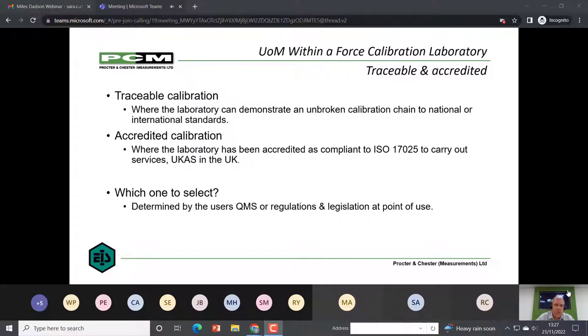And once you've decided, do you want a traceable or an accredited? And to be fair, most accredited calibration labs will offer traceable as well, and most likely be on the same equipment. Which one do you select? It is entirely down to either the quality management system of the company carrying out the use of the calibrated device, or the regulations and legislation covering the calibrated equipment at the point of use.